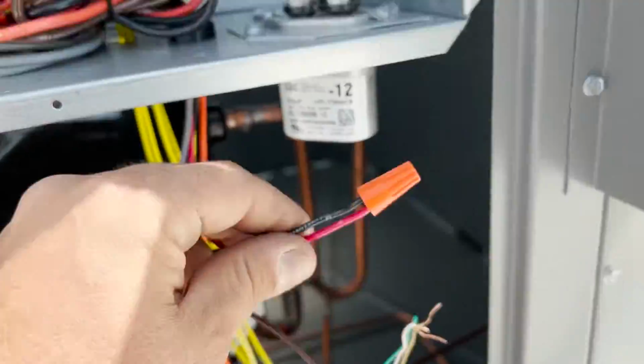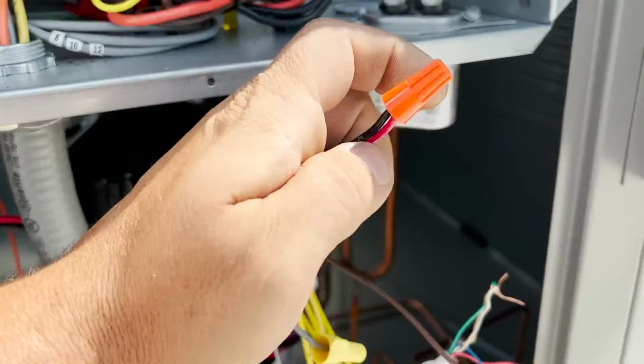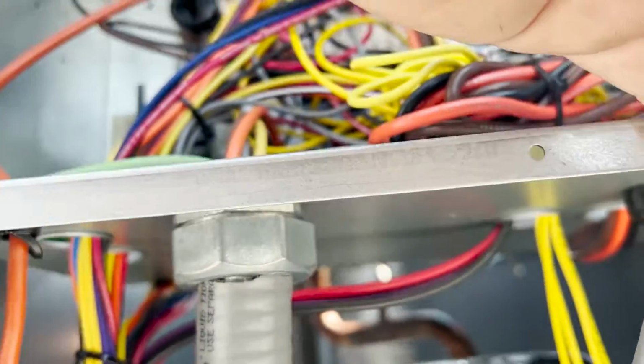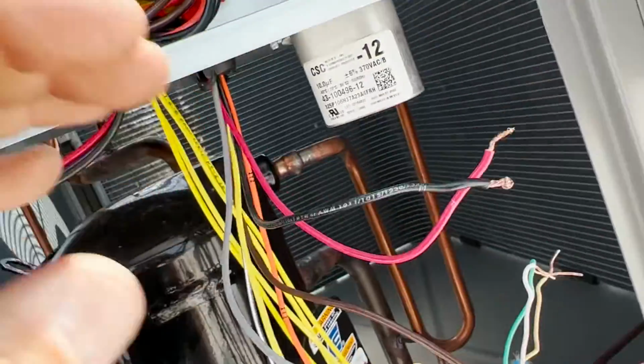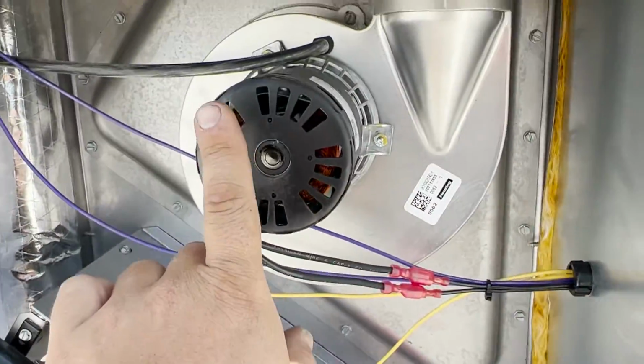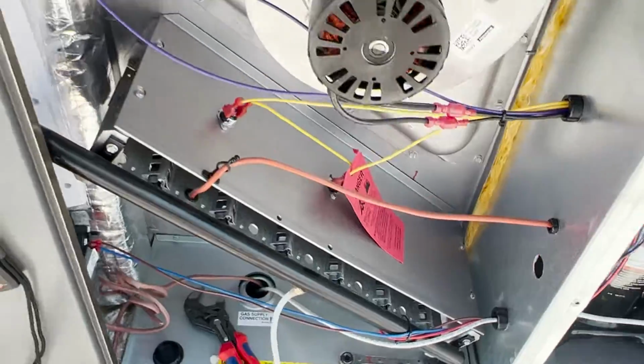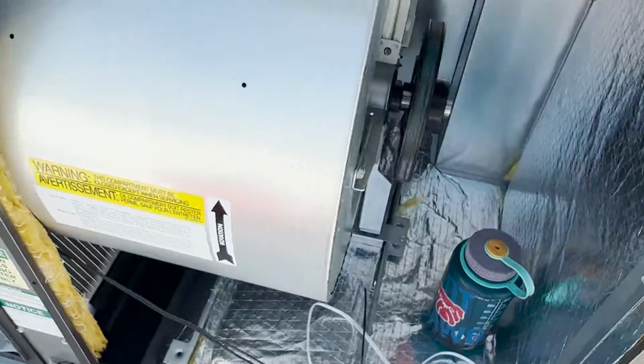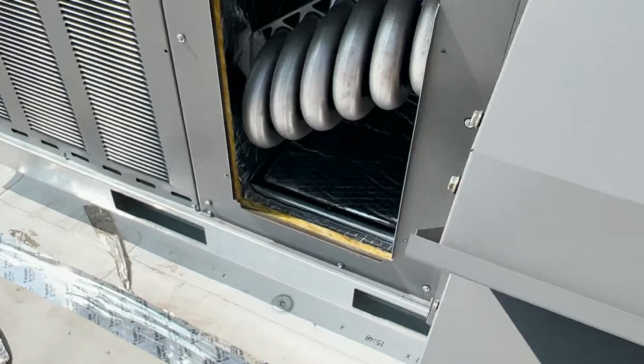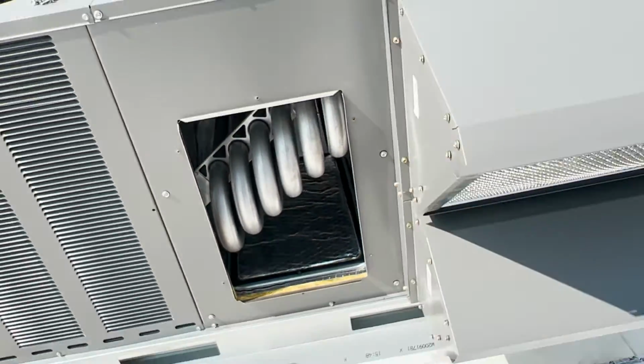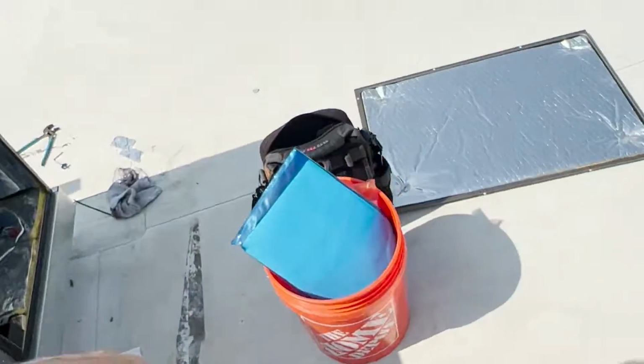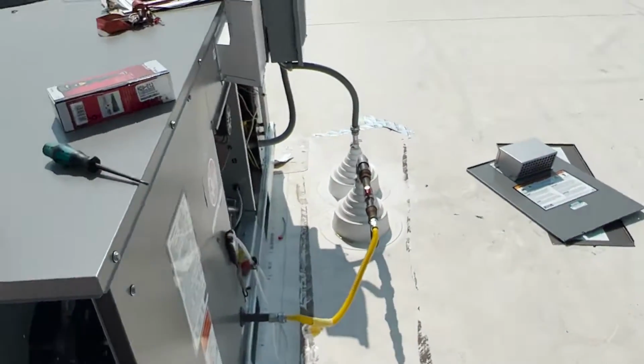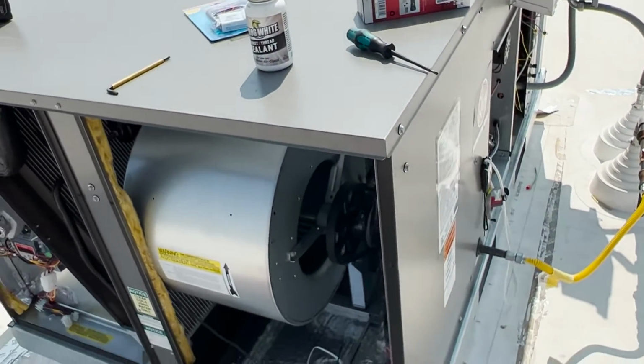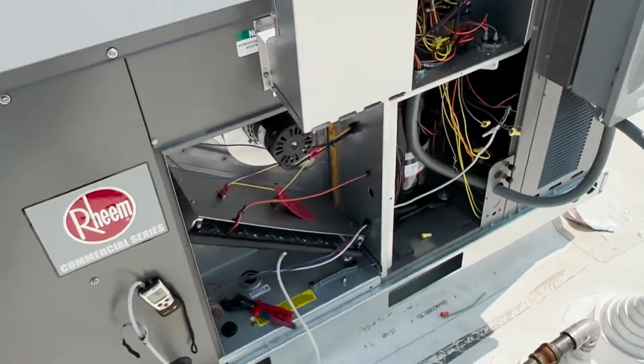When I disconnect from heat, I don't like to just shut it off because the heat exchanger needs to cool down. So let's try to do this with one hand. We're gonna pull the wire nut off and just separate these two. It's gonna shut off our burn compartment, but continue to keep our blower motor running so we can cool this heat exchanger down. Because if you don't do that, if you just power it off, you'll hear the heat exchanger like an old house. Creak, crack, creak. There's no need for that.